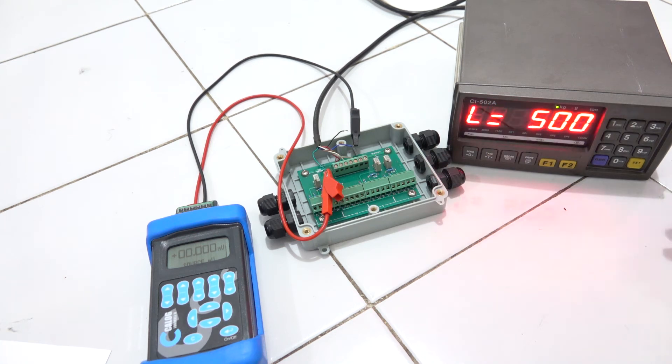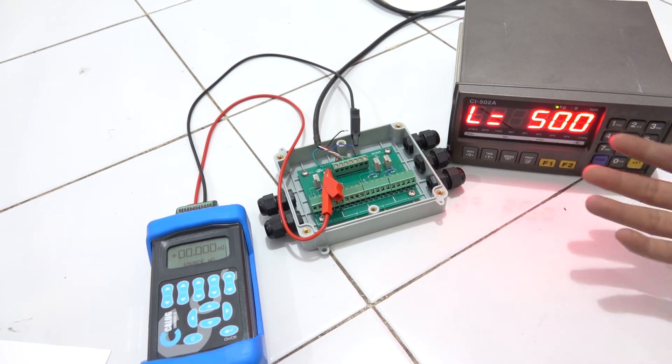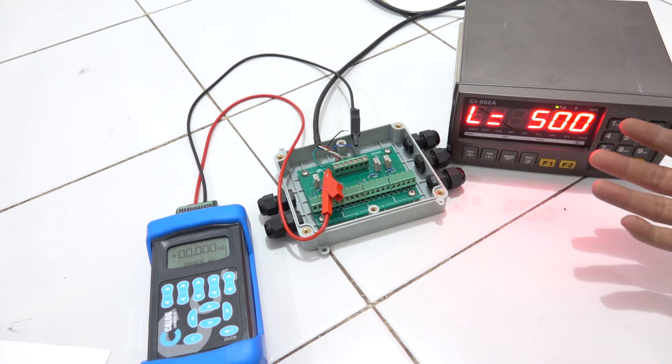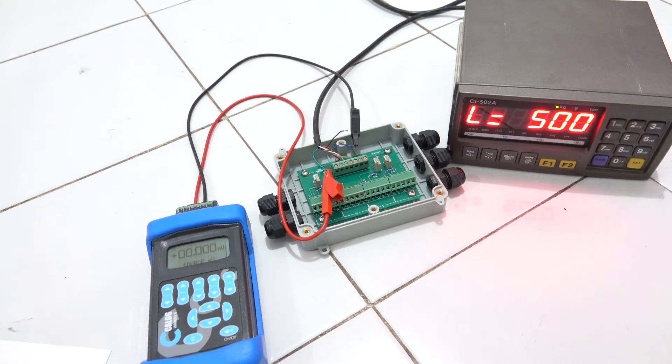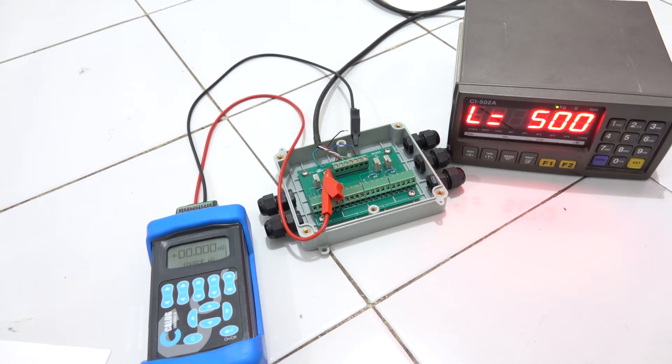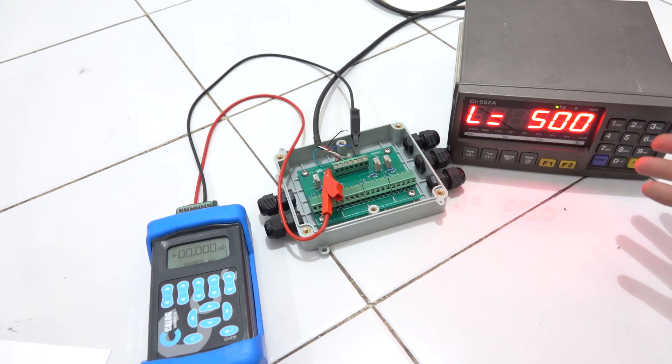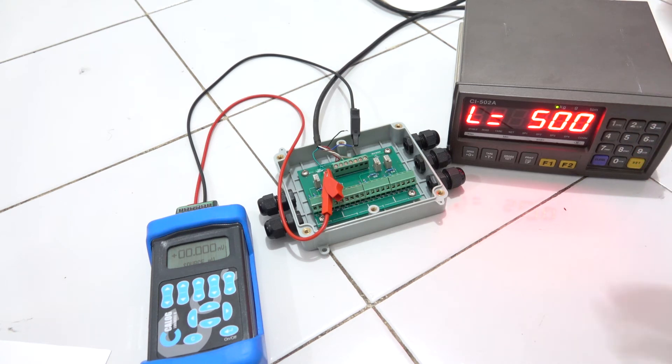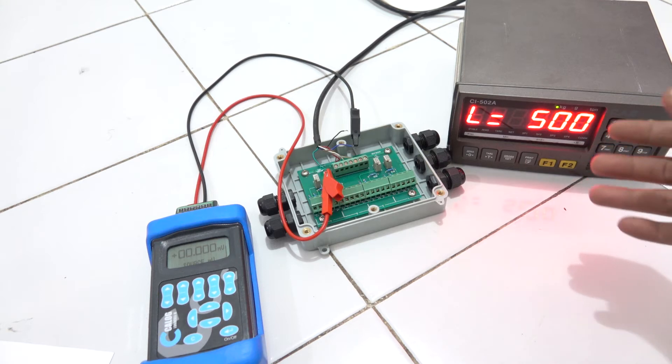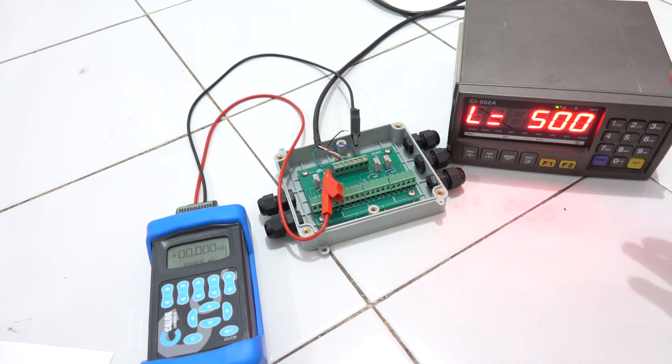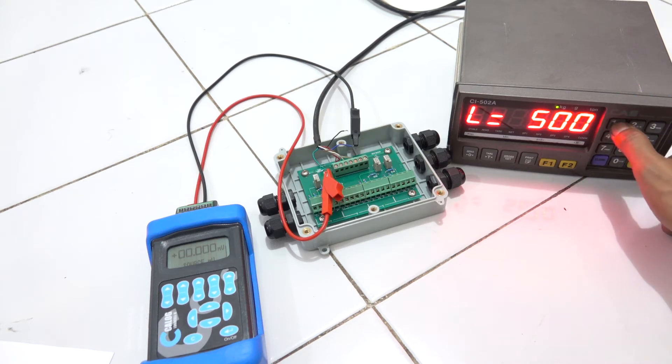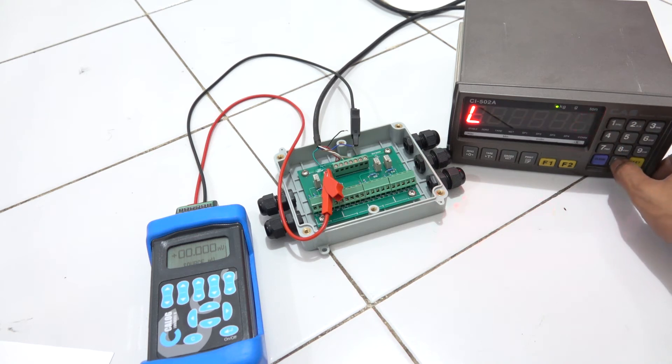Good. Now the span calibration means how much weight you want to use to calibrate. In regulation, at least 10 percent of maximum weight. We have a maximum weight capacity of 500 kg, maybe you need 100 kg. That's 20 percent. Let's say I put 100 kg.